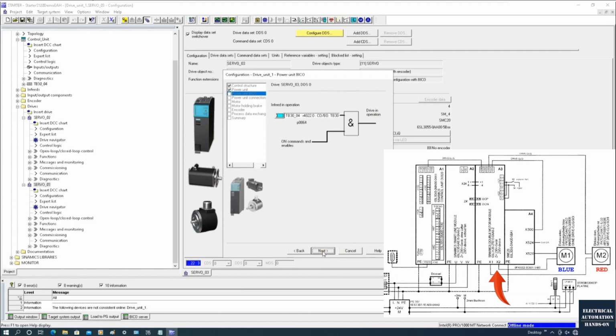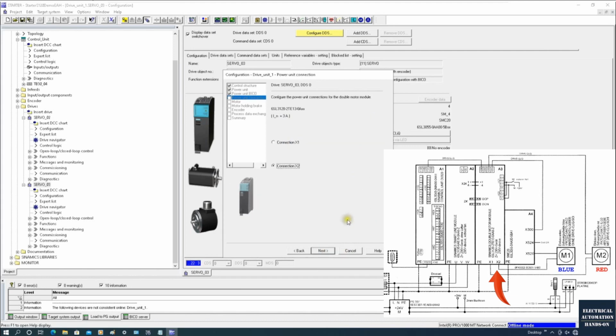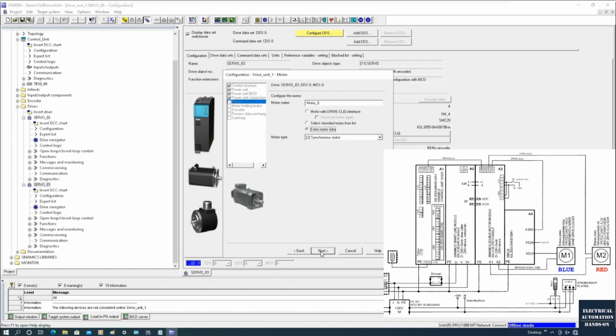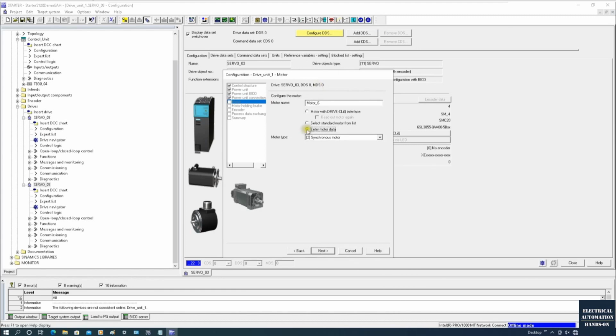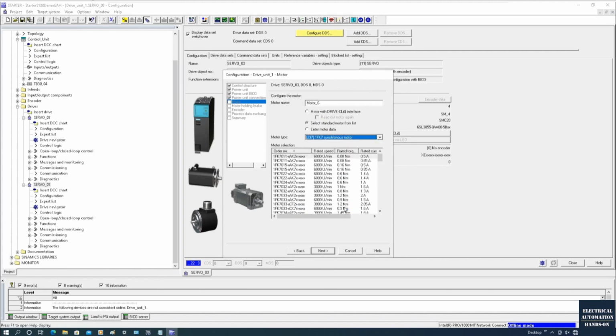The next step is the connection number. According to this drawing, this is connection 2. Since Servo 3 comes from the second connection, that is the X2 connection. And then let's go configure the motor. In this case, I'm connecting a synchronous motor, so that's the 1FK7. Let's pick the servo motor that I used in this demo site. In this case, I'm using this 1FK7 servo motor. It's 0.6 newton meter, 1.4 amperes.